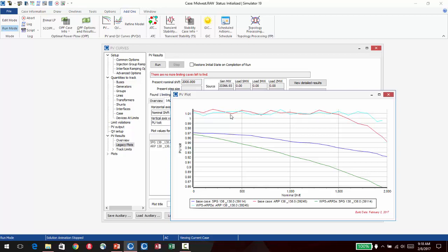When you see your plots up here for the Arpin bus look like this, what that means is there was some form of voltage regulation going on. So you can see where the steps were occurring, where we had some voltage controller that kept switching in either taps on a transformer or adding VARs at a switched shunt to try and hold the voltage up. But eventually it runs out of capability to do that.